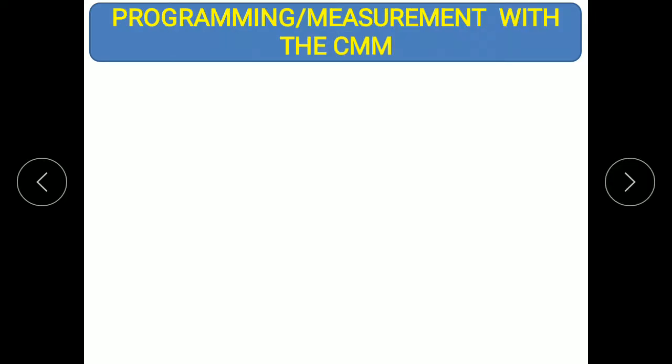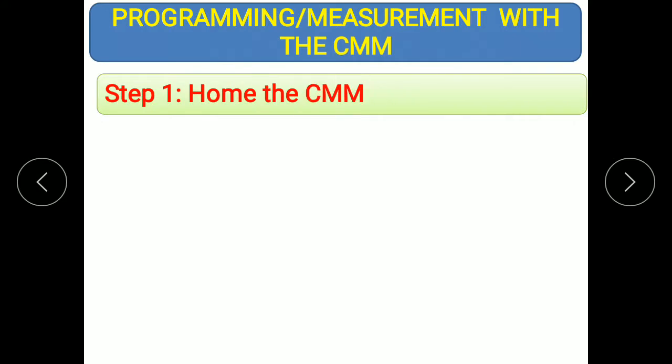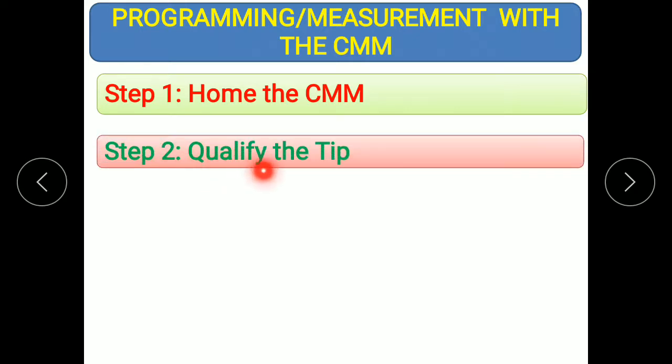The steps involved in measurement using a CMM are as follows. Step one is to home the CMM — set the coordinate origin. Step two is to qualify the tip — check the stylus properly to ensure it is correctly set and qualified for inspection.